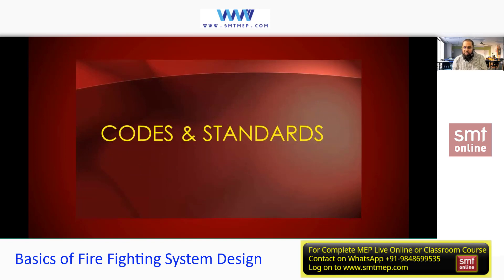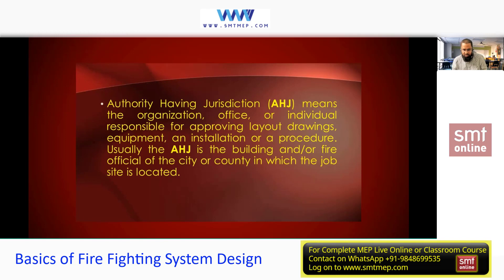Do you know the difference between codes and standards? A standard is a general reference — like NBC or NFPA. A code is mandatory and required to be used in a project. For example, if your local authority accepts NFPA, then NFPA becomes the code for your project. Codes are mandatory. Next, AHJ — Authority Having Jurisdiction — is your local authority. For example, if you're designing a project in Dubai, you must take approval from that local authority, which we call AHJ. They are also responsible for on-site inspection.